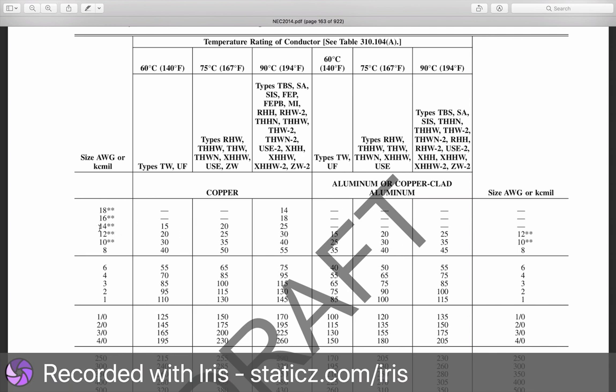Let's look at one we're familiar with, 14 gauge right here, and we're going to talk about these asterisks in a minute. 14 gauge is actually good for 25 amps, as you can see right there. We only put it on a 15 amp breaker, and part of that is because of these asterisks. They explain that. It gives you a little bit extra, just in case we have certain conditions where we have to do something called derating, taking down the value of the conductors because of external situations or because of grouping too many conductors.